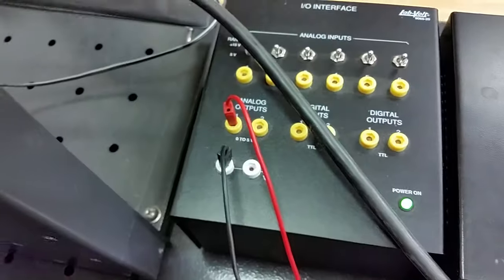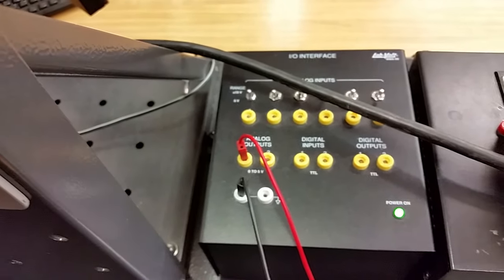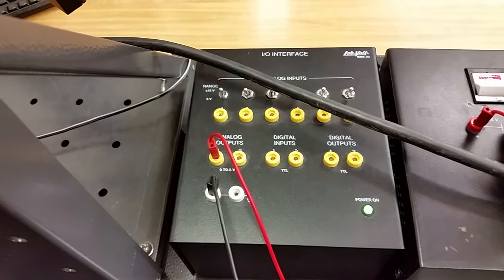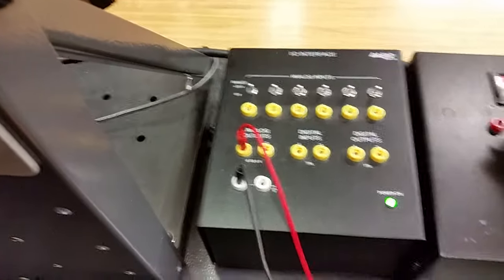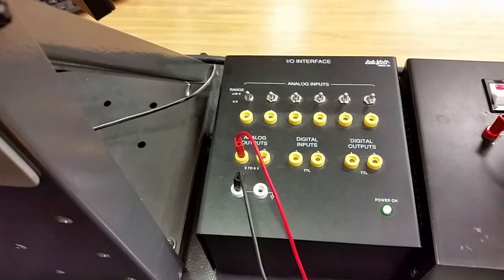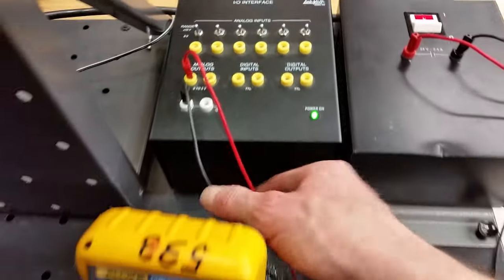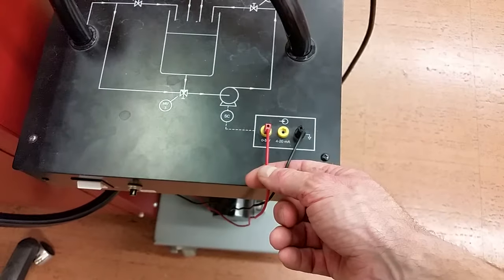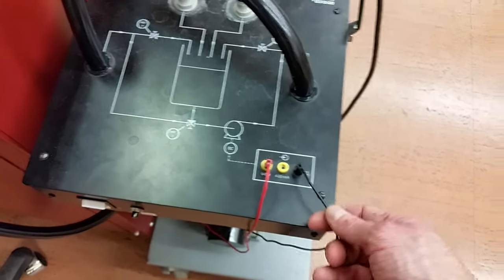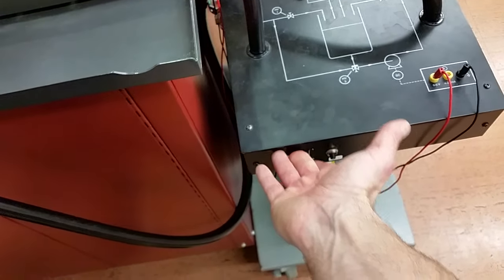If you screw up that connection — putting them reversed — you won't get full control over the drive. You'll call me over saying you can't control the pump from zero to a hundred percent, and I'll say you haven't hooked it up properly. So: zero-to-five to zero-to-five, and common to common. We don't have to do anything else to the IO interface for now — we just have those two wires going over to the pump.